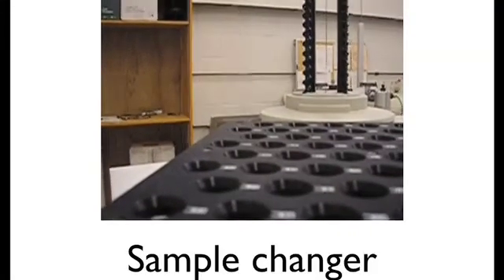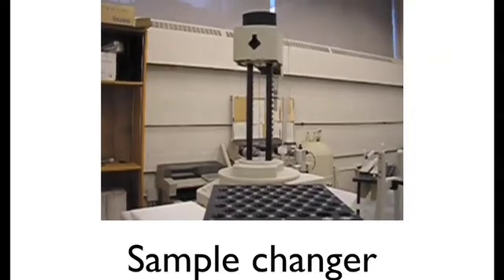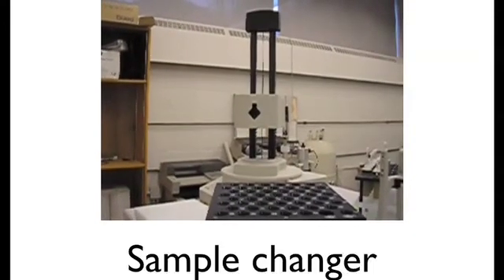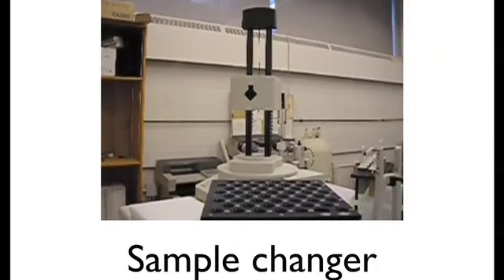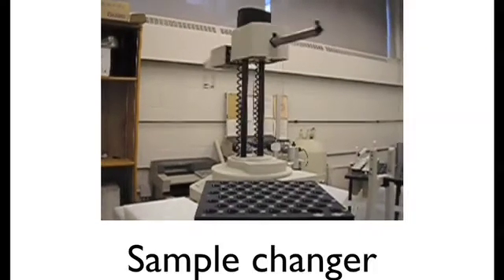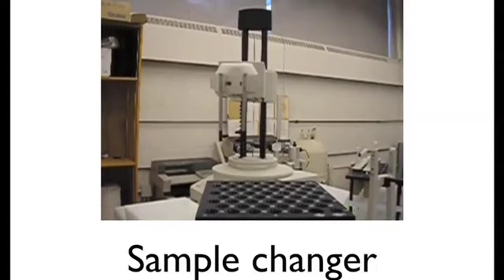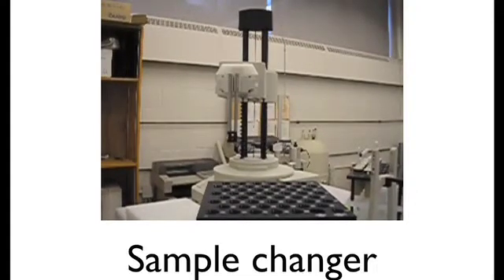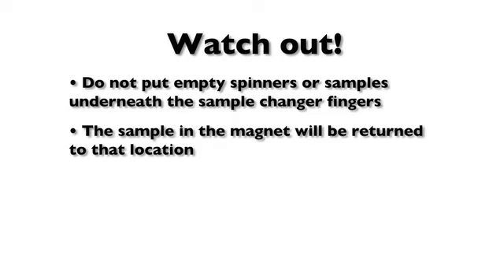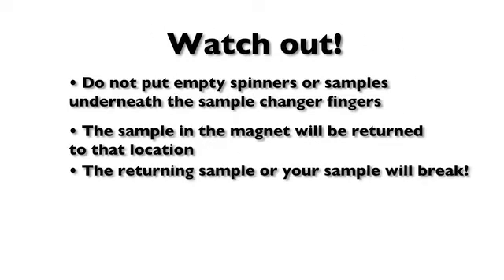Here's a quick video of the sample changer, putting a sample into the magnet. The robot fingers return to the location of the sample that was put into the magnet. So do not put samples or spinners underneath the robot fingers. There's always a sample in the magnet, and that sample will be returned to the location under the robot fingers. The returning sample will collide with anything in its path, breaking your sample or the other sample. Automation will then stop.